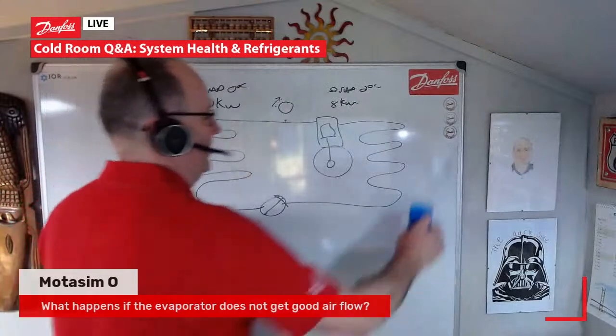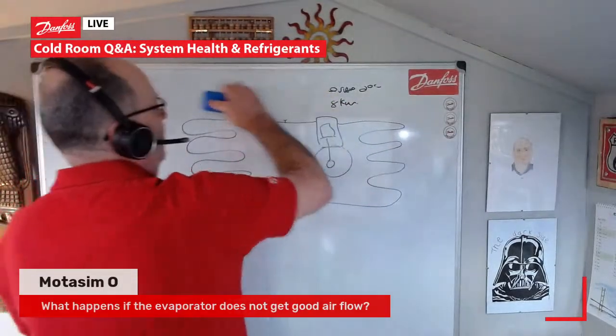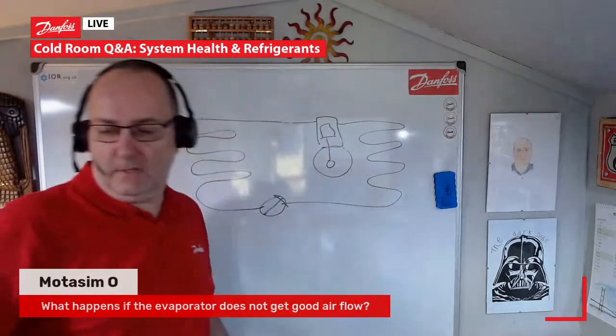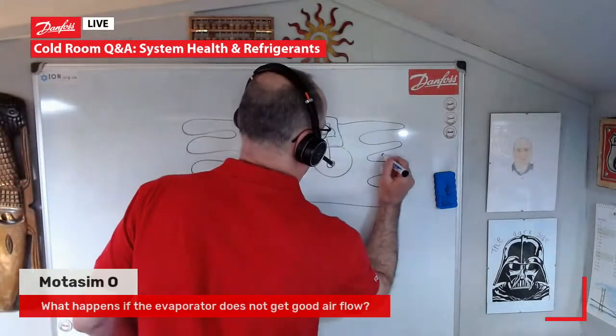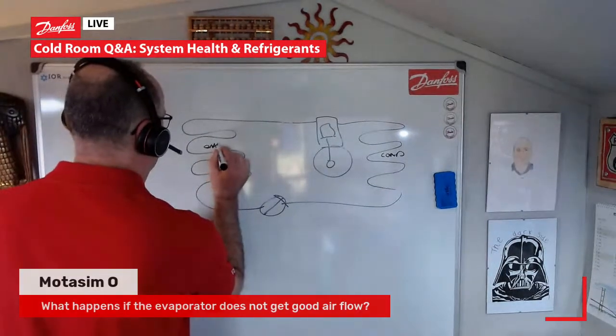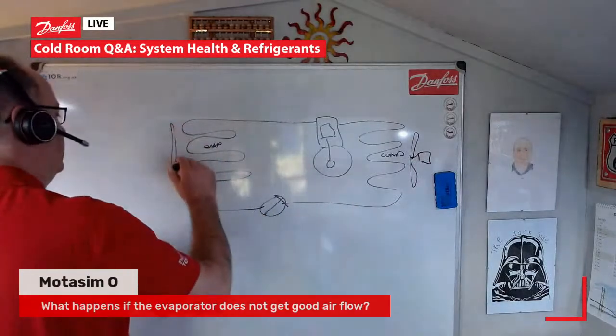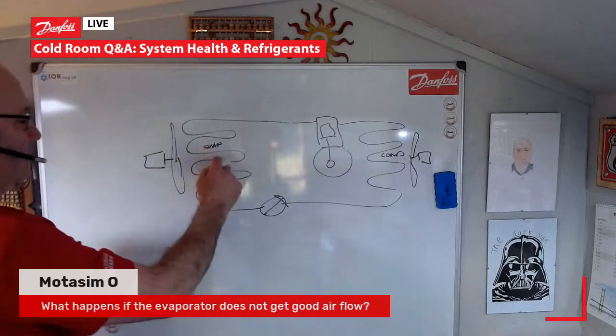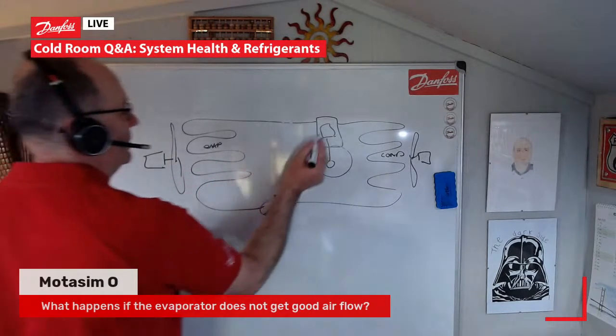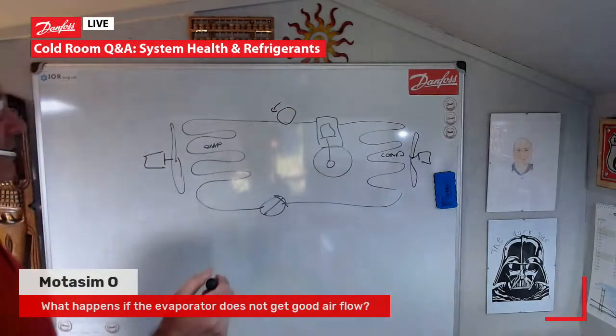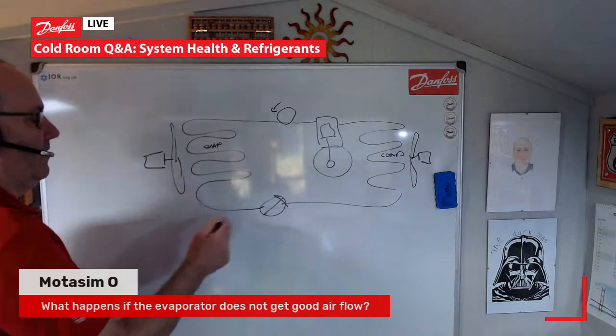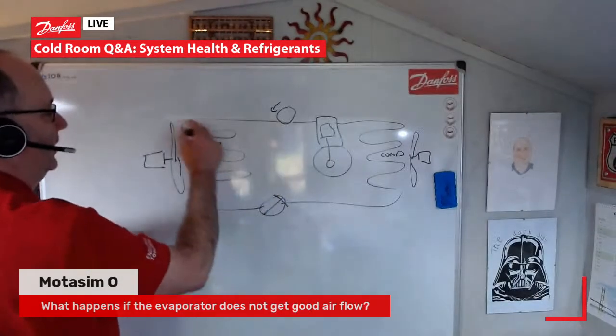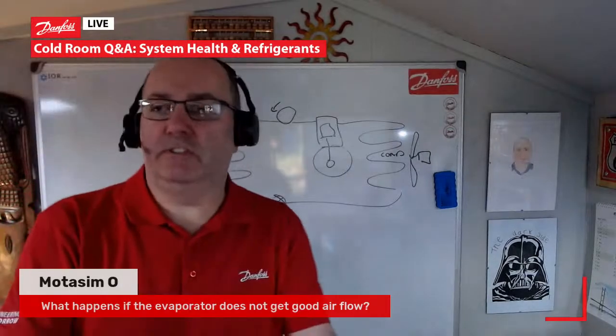Okay, what happens if the evaporator does not get good airflow? Yeah, one of my favorite topics, I think, is airflow. Let's do it on the whiteboard again. Actually, we can keep that picture up there a little bit. Let's just get rid of our capacities. So we've got our refrigeration system, our compressor, our condenser, our evaporator, a fan on our condenser, and a fan on our evaporator. If we don't get good airflow on the evaporator, basically the suction pressure coming back to our machine is going to fall. The reason it falls is because we're not providing that heat exchange on our evaporator. So the suction pressure will fall and the evaporator will ice up, basically, so we get less capacity from our machine.